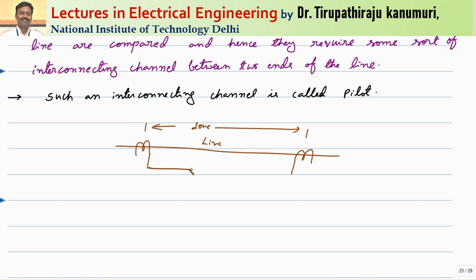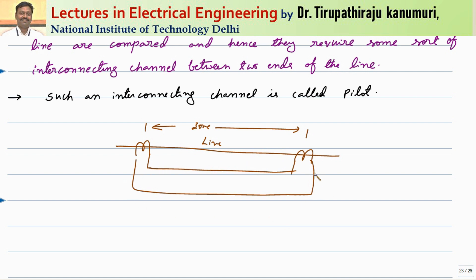The connecting channel can use pilot wires connected directly — this is the circulating current scheme — or crossed, which is called the voltage balance scheme. The problem with pilot wires is they must run over long distances since transmission lines are very long. The disadvantages are: first, running cables along the transmission line is costly; second, the pilot wires have capacitance and resistance effects, which introduce measurement problems and overloading of CTs. That is why this wire scheme cannot be used for lengths greater than 30 kilometers.